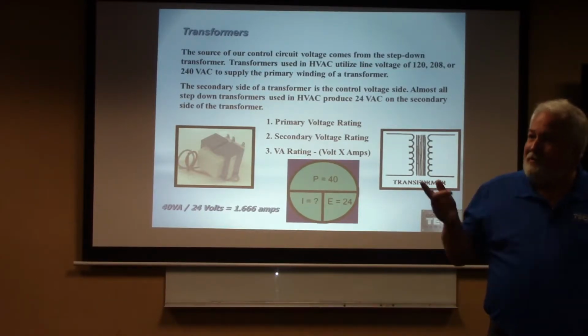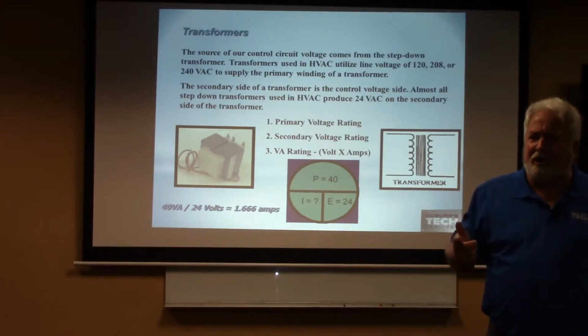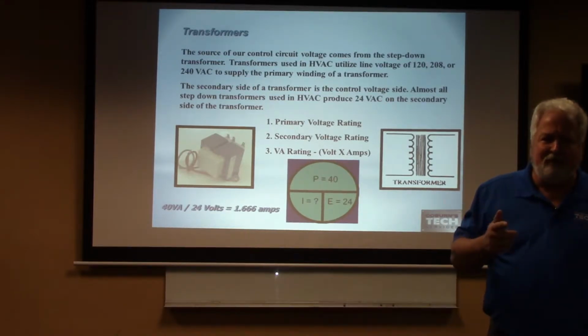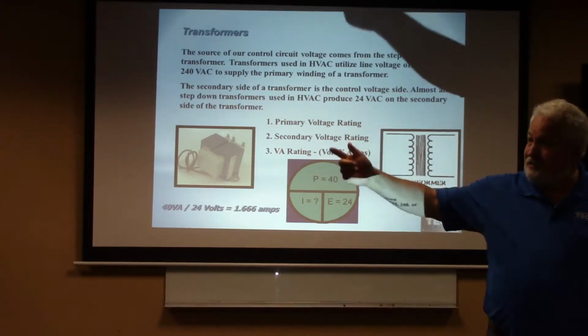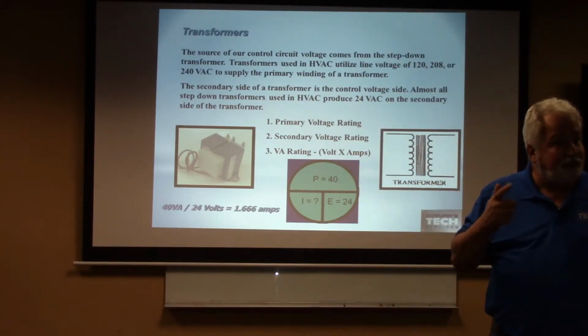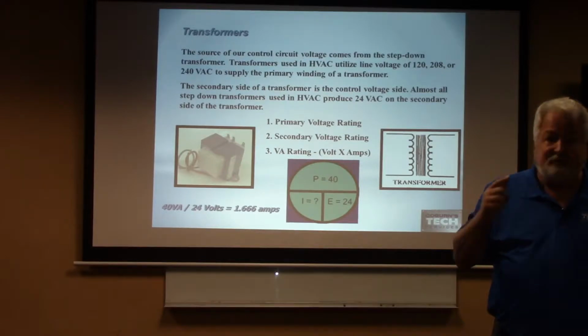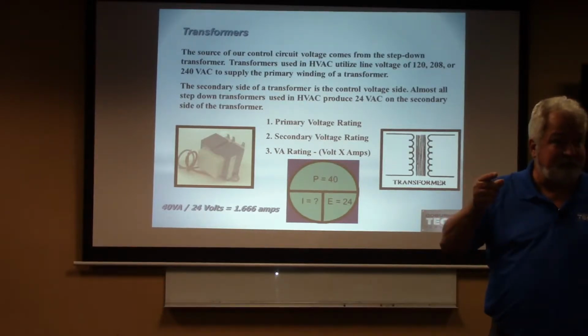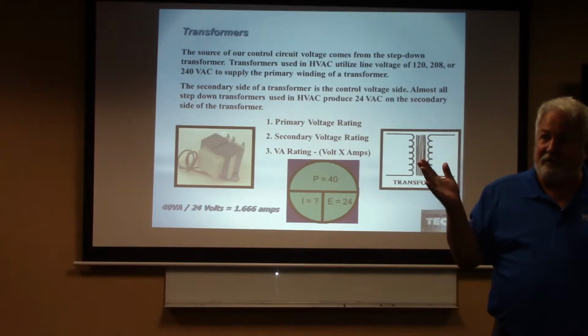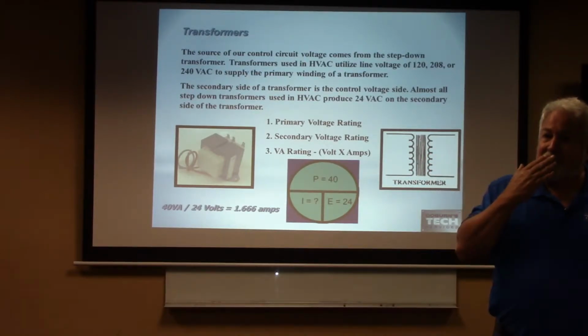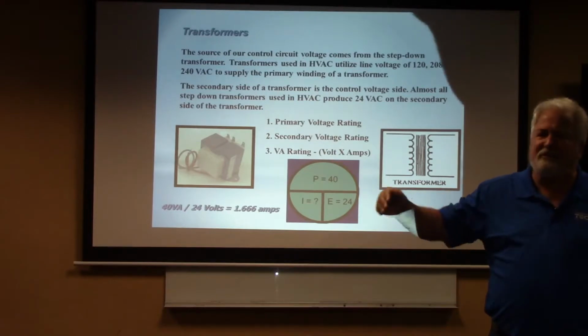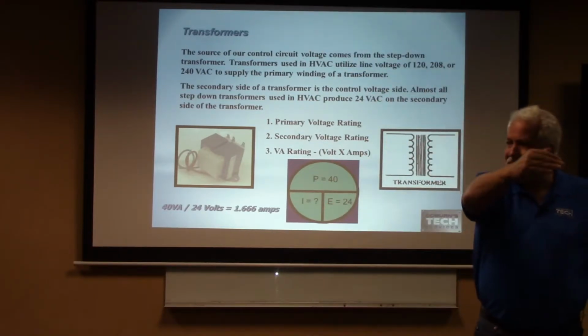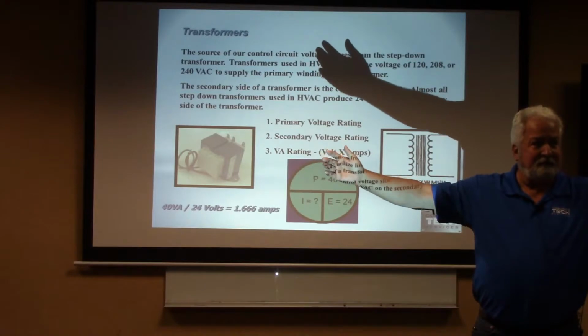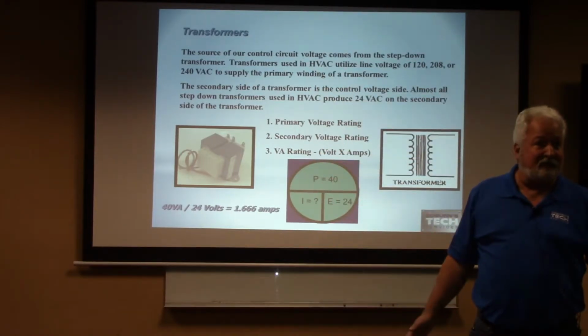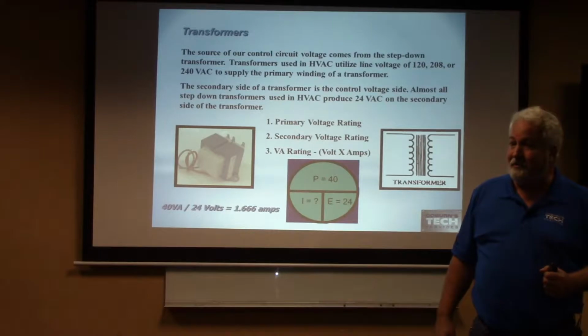So that would mean that I'm running more current. That would mean that I might have too many loads, or I have a short in there. Is that right? Something's causing the current to increase. Is that making sense? How good is this piece of information? Good. So you saw that you had everything was okay, but somebody had added a bunch of those zone dampers, right? You know now you have too many loads in that circuit. That's what's going to cause it to go out. Is that right? You measured 2 amps on there.